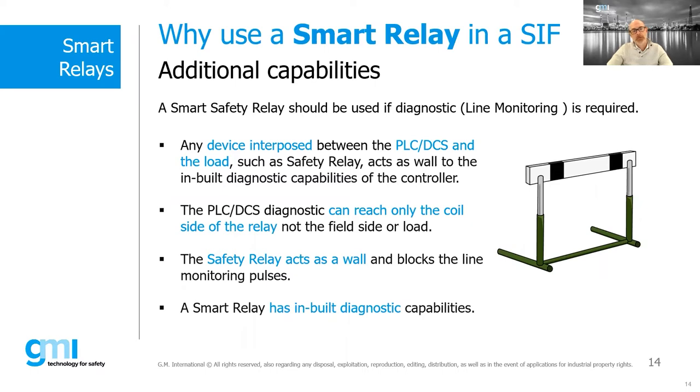Massimo? Yes, but what is the smart relay? The smart relay is a relay that guarantees a specific safety function, like a typical safety relay, but in addition, it has the ability to perform complete field diagnostics. By complete diagnostic, we mean a diagnostic that includes constant monitoring of line and load functions in both operating conditions of the relay, on and off status.